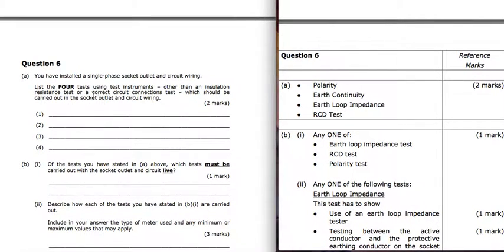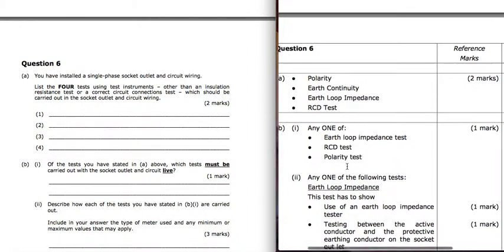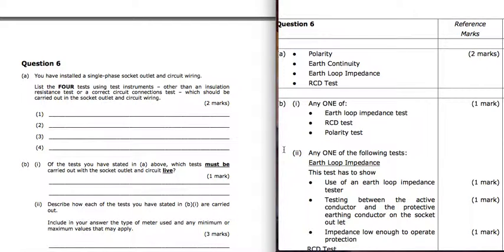Question 6. You've installed a single phase socket outlet and circuit wiring. 4 tests using test instruments other than insulation resistance. So there's our 4 there: polarity, earth continuity, earth loop impedance, RCD tests. Of the tests, which must be carried out with the circuit live? So we're only looking for one. So we can have earth loop impedance test, RCD, or polarity. So they can be carried out live.